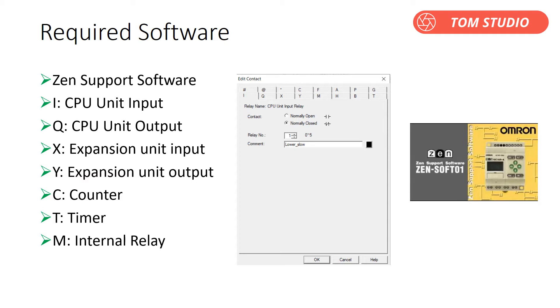In programming, normally: I means physical CPU unit input, Q means physical CPU output, X means expansion IO unit input, Y means expansion IO unit output, C means counter, T means timer, M means internal bit. Both timer and counter instructions are output type, which means you must set a condition in front of the counter or timer, then use their contact to control outputs.